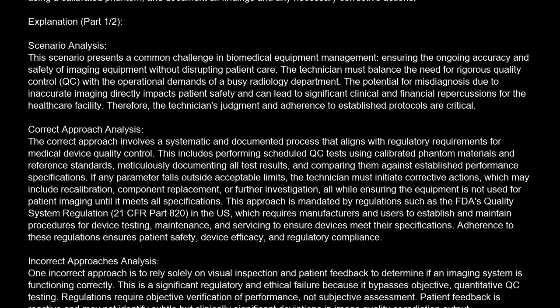The correct answer is B. Perform a full suite of scheduled quarterly QC tests immediately, including objective measurements of image resolution using a calibrated phantom, and document all findings and any necessary corrective actions. Explanation: scenario analysis. This scenario presents a common challenge in biomedical equipment management, ensuring the ongoing accuracy and safety of imaging equipment without disrupting patient care. The technician must balance the need for rigorous quality control, QC, with the operational demands of a busy radiology department.